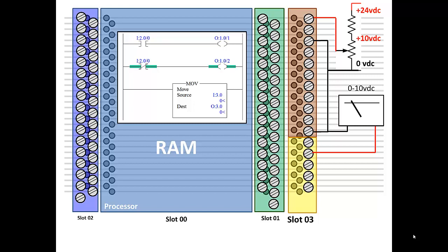If you're not familiar with the potentiometer, maybe that symbol threw you for a loop. That's the squiggly line with the arrow pointing to it. The arrow touching the resistance symbol in the voltage divider represents the wiper arm in the pot. As you rotate the shaft of the potentiometer, the wiper arm moves up and down the resistance, dividing the 10 volts DC within a range of 0 to 10 volts. If the arrow is all the way at the bottom, then you get 0 volts into the card. If it's all the way at the top, you get 10 volts in.